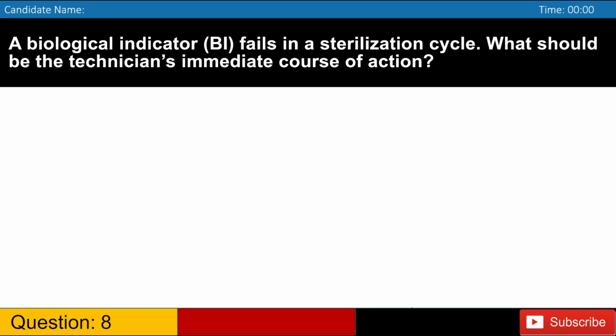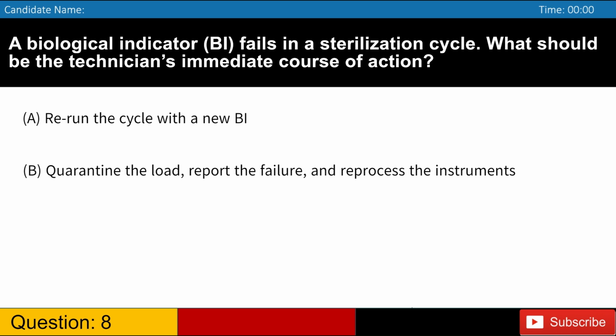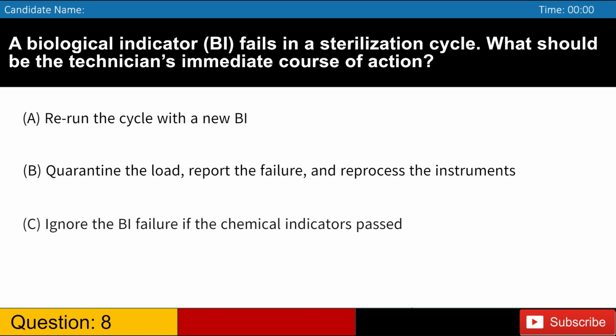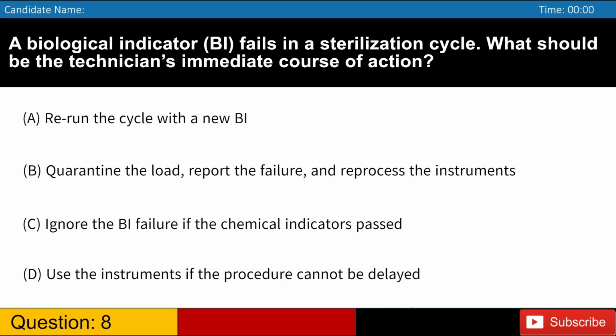A biological indicator, BI, fails in a sterilization cycle. What should be the technician's immediate course of action? A. Rerun the cycle with a new BI. B. Quarantine the load, report the failure, and reprocess the instruments. C. Ignore the BI failure if the chemical indicators passed. D. Use the instruments if the procedure cannot be delayed.